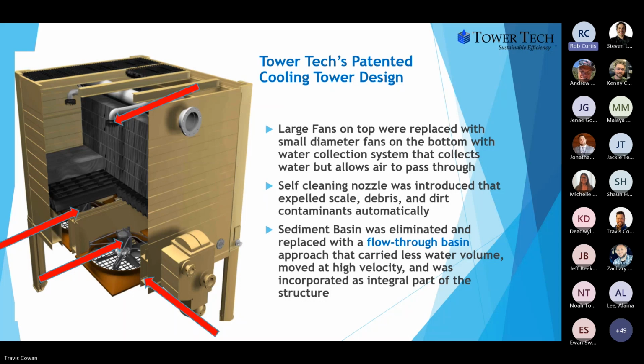And then the third thing was traditional cooling tower basins are typically open sediment basins. That's what they have been designed to do. And I might just backtrack just a second. The reason we developed this is we were a service company. As a service company, we started seeing these problems, and that caused us to move toward innovation to solve these issues. But the sediment basin, we eliminated that and replaced it with what's called a flow-through basin that allows you to move the water very rapidly, which allows us to reduce a lot of things from a consumable in a tower.